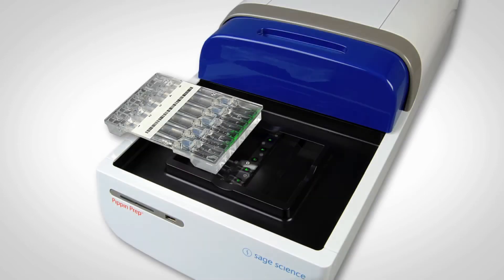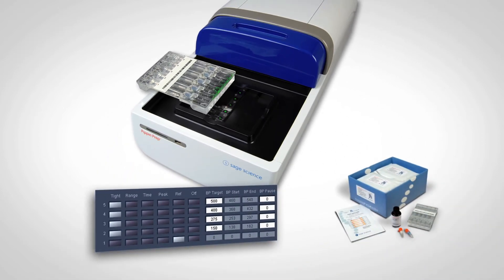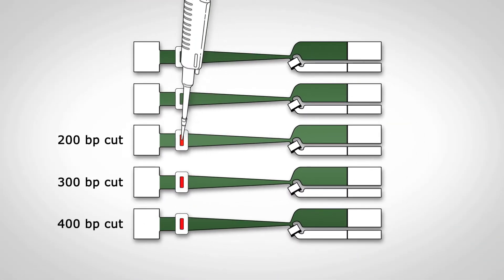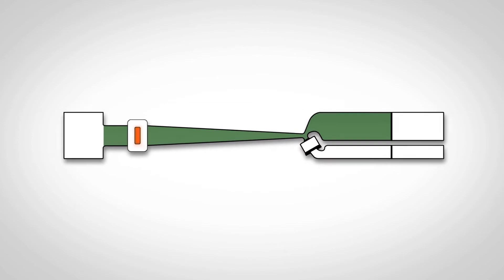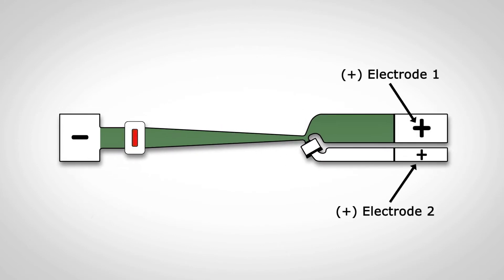The heart of the Pippin is a disposable agarose gel cassette, which collects fractions from four samples in sequencing-compatible buffer. The user simply enters a target value or a base pair range into software, and pipettes samples into four wells, much like one would on a slab gel. A DNA reference marker is loaded into a fifth lane. Each sample lane is physically separate from its neighbors and features a branched channel which terminates with two positive electrodes.